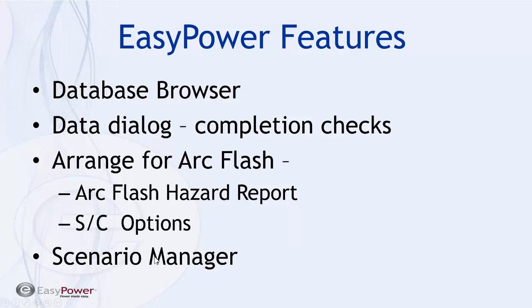There's also a facility built into the database edit called Scenario Manager, which lets us set up basic configurations that may even exist on a temporary basis in our system. The tool automatically compares incident energy calculations, giving us the ability to do what-if comparisons—not necessarily error checking per se.